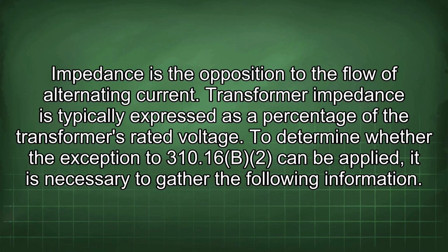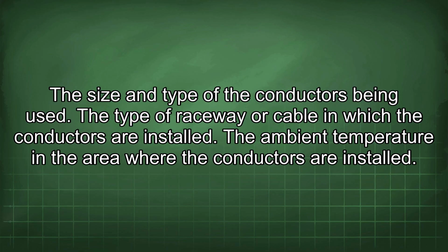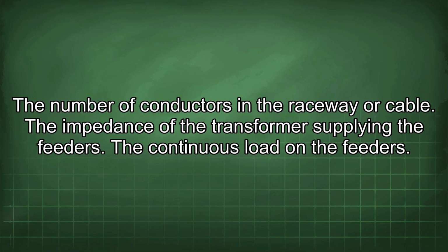To determine whether the exception to 310.16(b)(2) can be applied, it is necessary to gather the following information: the size and type of the conductors being used, the type of raceway or cable in which the conductors are installed, the ambient temperature in the area where the conductors are installed, the number of conductors in the raceway or cable, the impedance of the transformer supplying the feeders, the continuous load on the feeders.